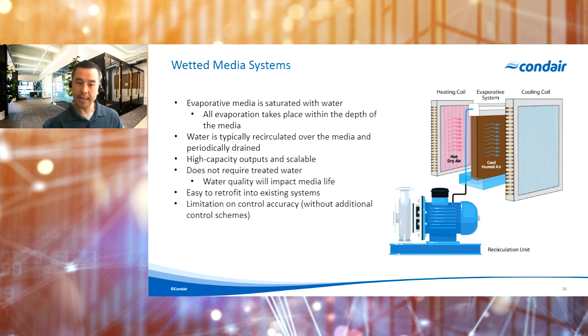Now, the thing to keep in mind here is that all of the evaporation takes place within the depth of that media itself. So if the system is designed and operated correctly, there really shouldn't be any water carrying past that evaporative section. That makes this type of system really great for retrofit applications as well, because you can typically fit these into a tighter space compared to some of the other adiabatic technologies that we'll talk about that do require a bit more unobstructed airway length.